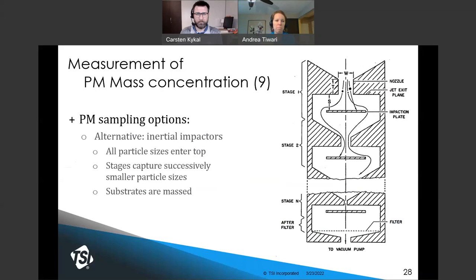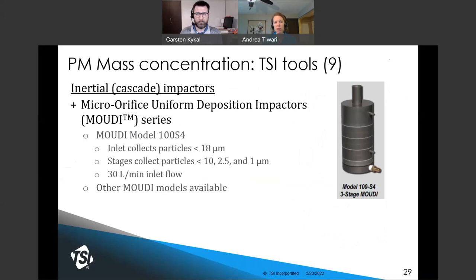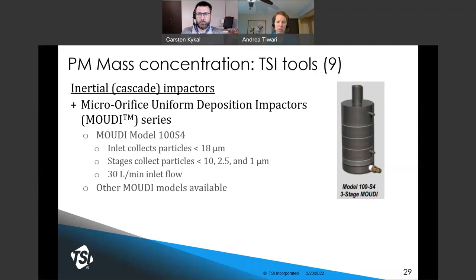TSI has a well-established line of cascade impactors called MOUDI impactors — microorifice uniform deposition impactors. These are widely used for ambient measurements, point source emissions characterization, and numerous other applications, cited in many dozens of peer-reviewed published papers. For brake wear measurement, we recommend the model 100S4, which has three stages with cut points at 10, 2.5, and 1 micrometers — a perfect fit for the PM10 and PM2.5 metrics required by the PMP protocol.